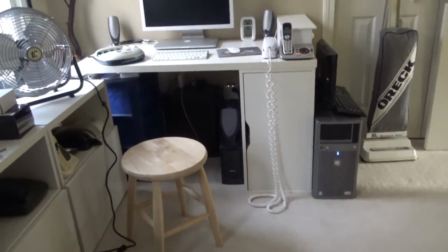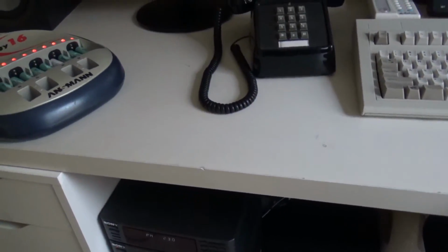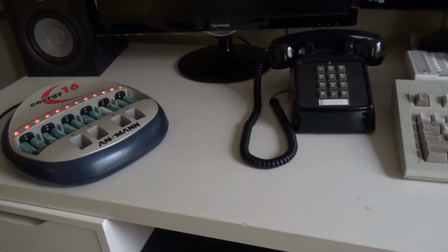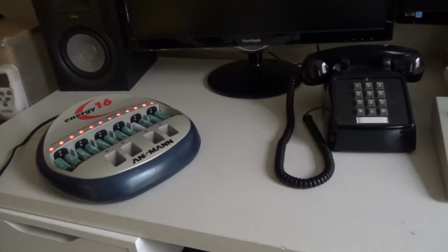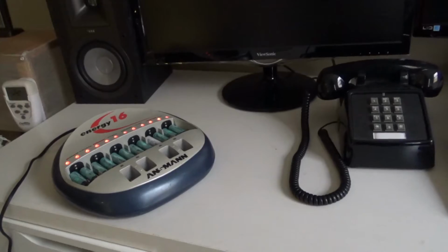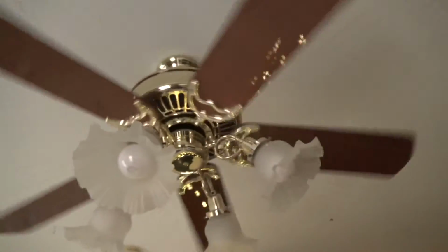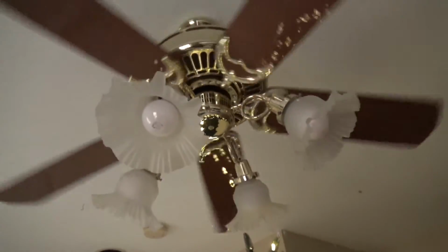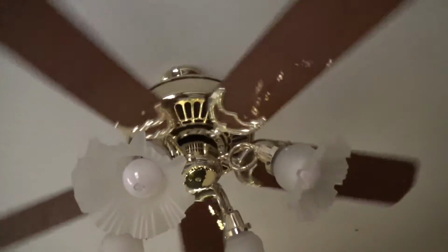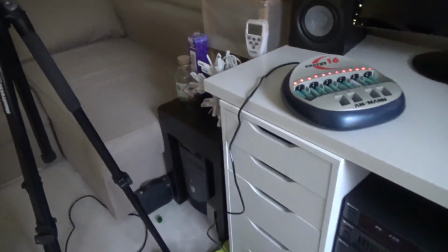So we'll allot an amp for the two battery chargers, 2.5 amps for that desk, 2 amps for this desk, which means we have a total of, if I can count, 1, 2, 3, 4, 5.5 amps consumed on a regular basis. Now this light is going to pull over 1 amp, so we're never going to use that light. The fan is about 0.8 amps, so that'll bring us up to 6.5 amps out of 15 already used.